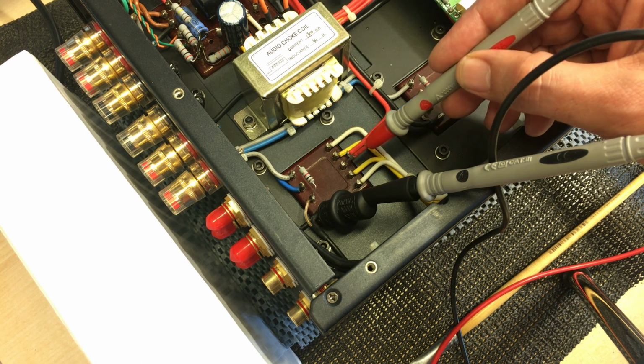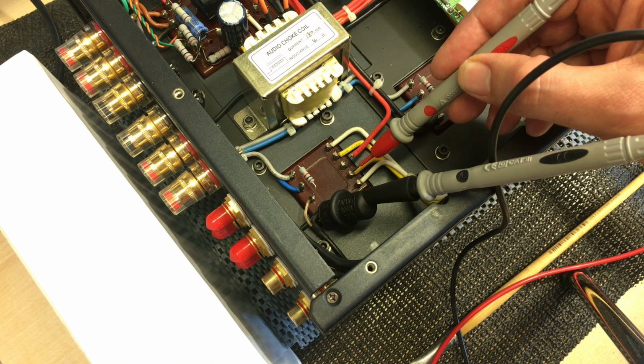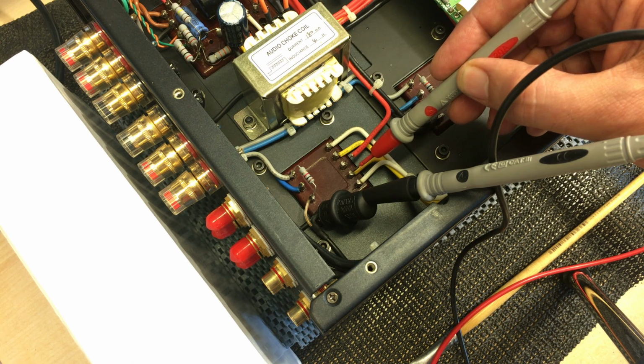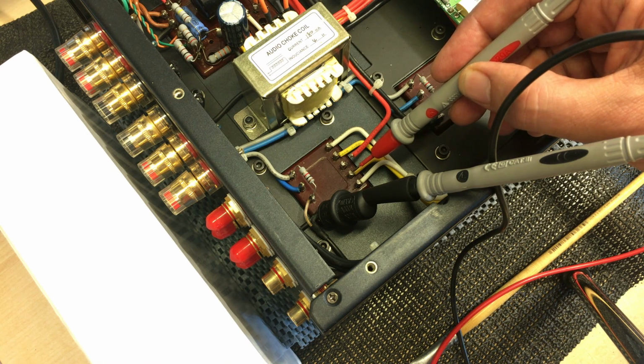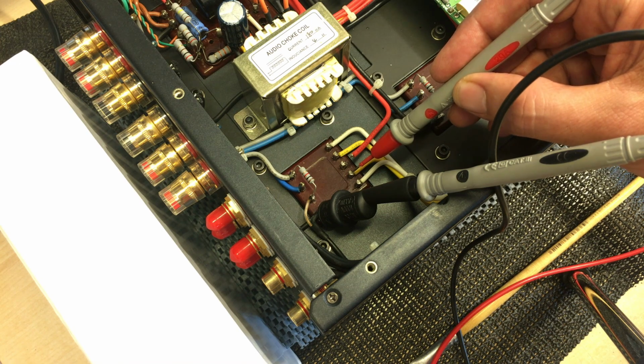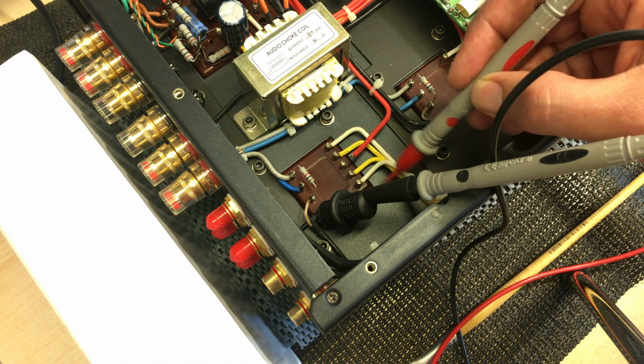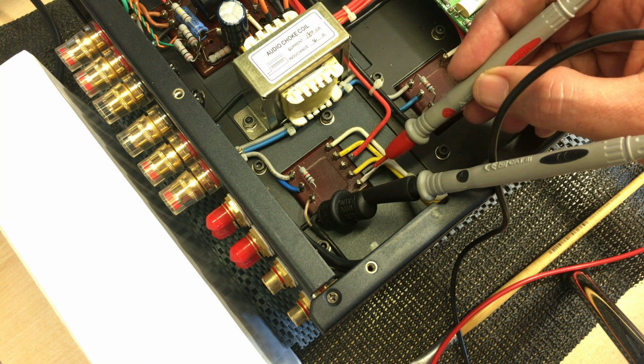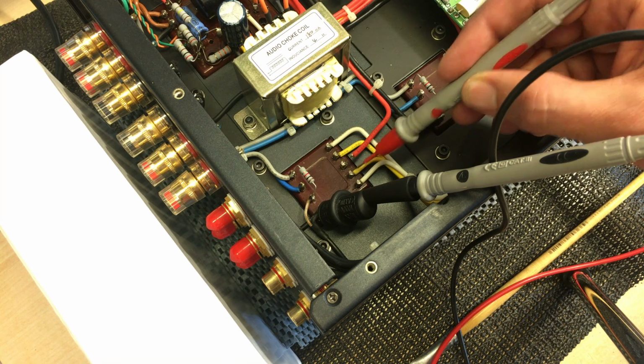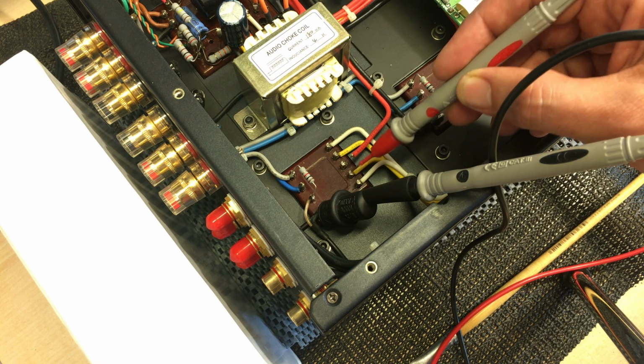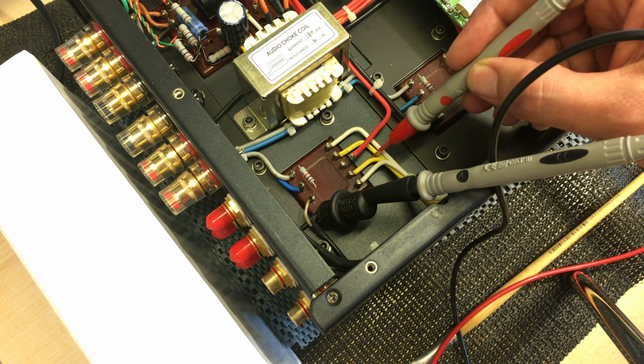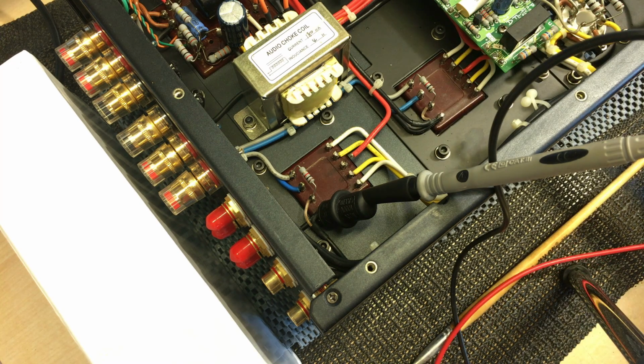There's been a spark with the casing of the transformer, which is connected to ground, so there's some leakage between this point and the chassis - my guess is carbon residue from some kind of short or spark inside, creating a path to the transformer's chassis on the other side. So now I'll disconnect this point from here to make sure it's actually on the transformer and not on this path over here. That'll be the easiest thing to do.